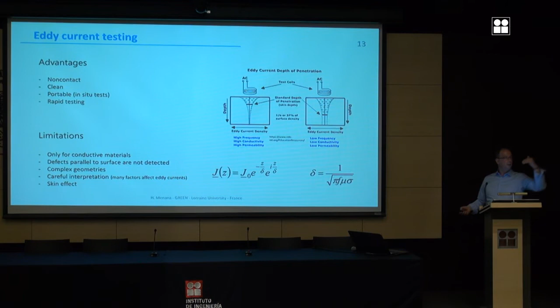You have studied skin effect, eddy current, since we are in the frequency domain, alternating current. 63% of the eddy current flows in the skin depth here, given by this equation. The skin depth is inversely proportional to the conductivity, the permeability, and the frequency. So sometimes, to saturate the material, we can add a static magnetic field, and then go deeper in the tested material.